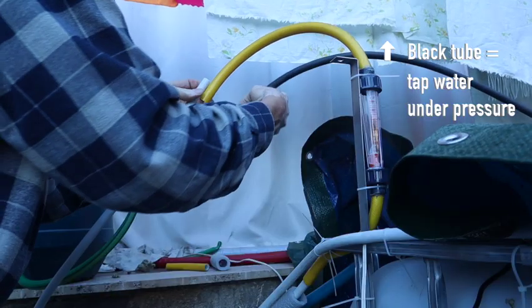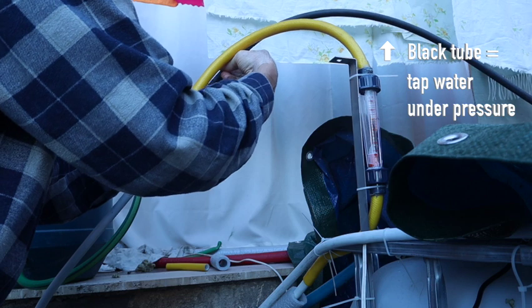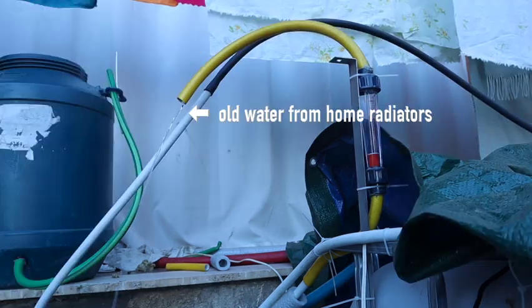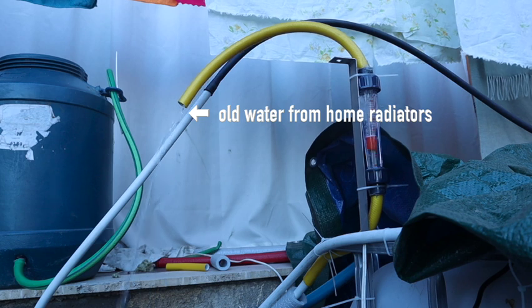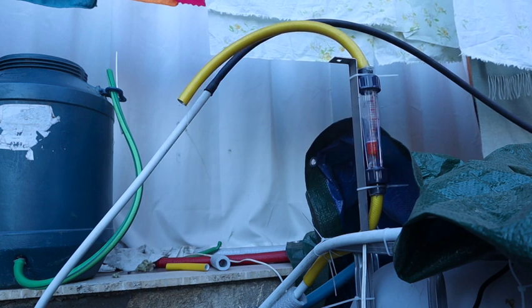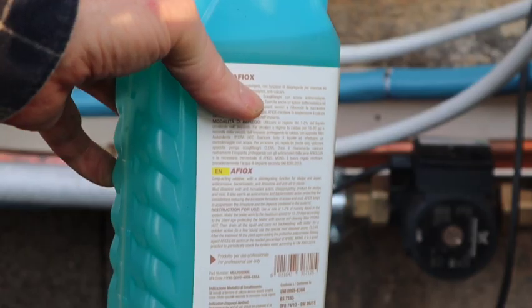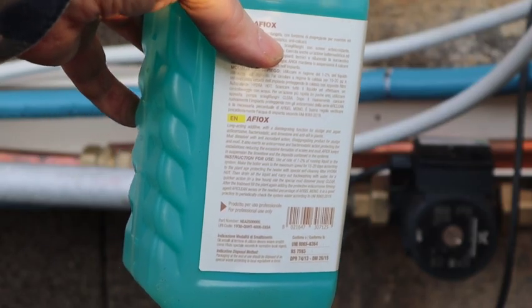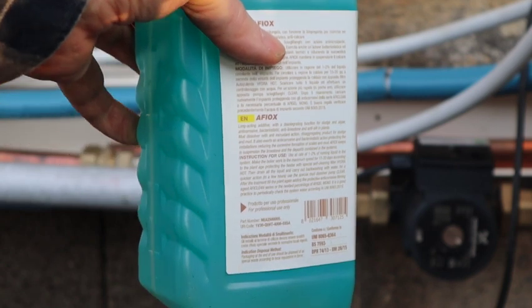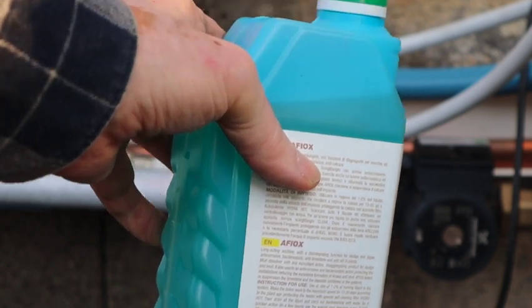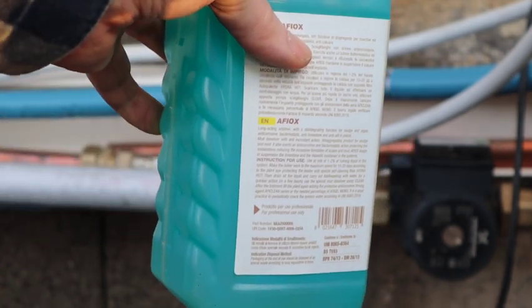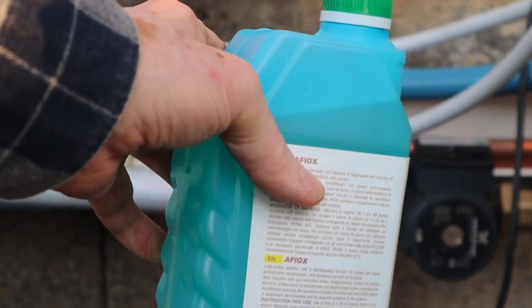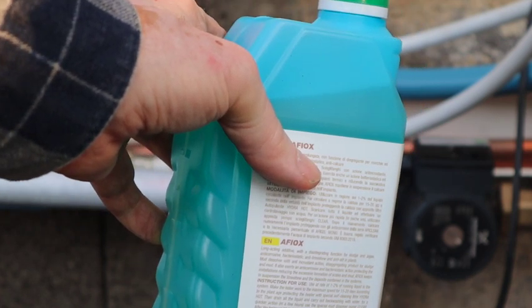When you cut the pipes, as I did, use the pressure of tap water to push out the old water, and look how clean it is. If the circuit is very old, the radiators might be of iron and are not resistant to tap water that may contain oxygen. It is good to protect it with an additive. I guess that a small, transparent container with 2 connections between tap and central heating circuit is the best way to get the additive into the circuit.